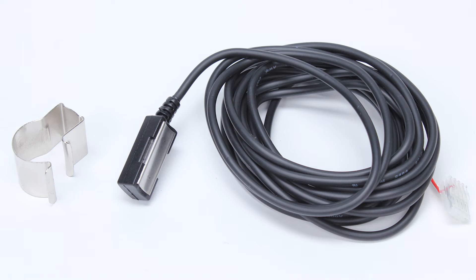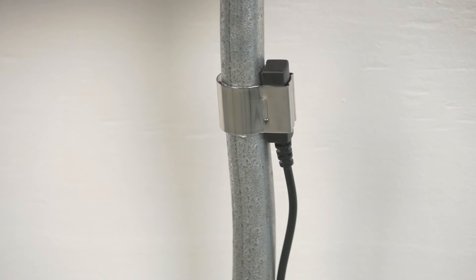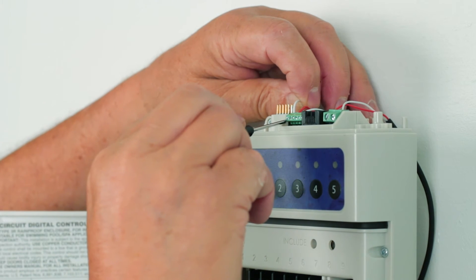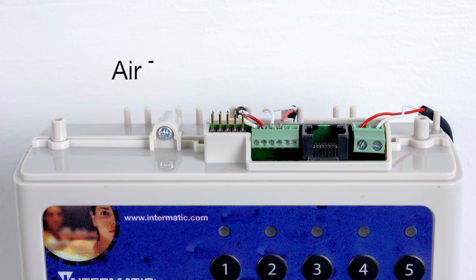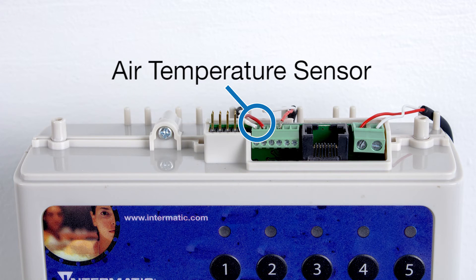The air temperature sensor is for the freeze control feature. Insert the sensor into the provided bracket and mount onto a piece of conduit. It needs to be in a position where it will read accurately, so do not put it close to a pump motor. To run the wire to the receiver, cut the plastic connector off and insert the wires into the two left terminals next to the water sensor. These are not polarity sensitive.